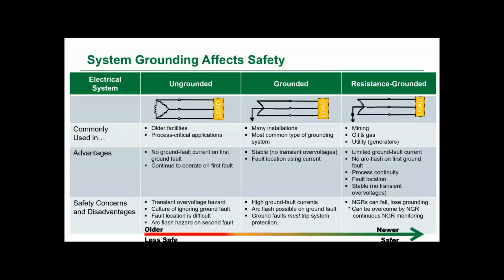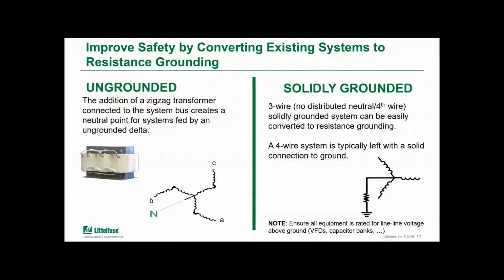And when you're using those types of systems, it allows you to eliminate, and if you can link that word back to the hierarchy of controls, eliminate the risk of an arc flash on that first ground fault and eliminate transient overvoltages because the system remains grounded and tied to ground. An ungrounded system that does not have an accessible neutral, it is possible to upgrade that to a resistance grounded system. And you can do that upgrade without having to replace the whole power transformer.